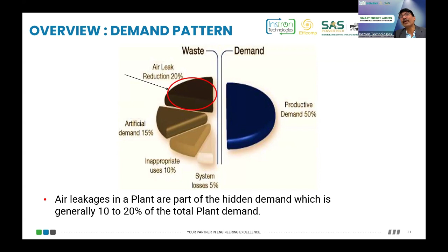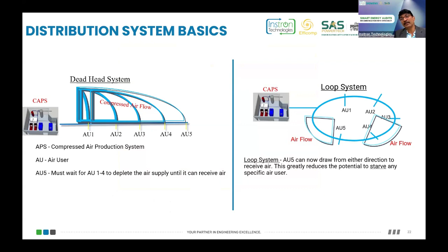Similarly, on the distribution network, over the period, whenever plants are designed, distribution systems keep on being added to rather than the complete system being remodified. And whenever we plan a new system, we generally focus on the primary investment in the piping and other areas rather than on the efficiency of the system as a whole. Here is an example. Whenever a new piping is laid out, a 3-inch pipe generally costs less than a 4-inch pipe. So there was a system designed to carry 2000 CFM. The purchase department will say, if it can be done with a 3-inch pipe, why go for a 4-inch pipe? We will be saving 6 lakh rupees compared to a 4-inch line.